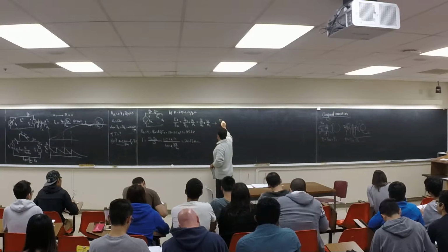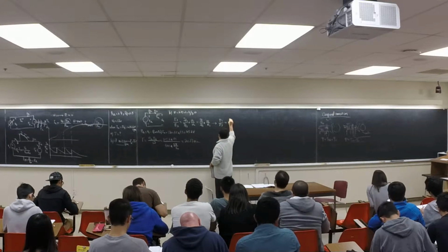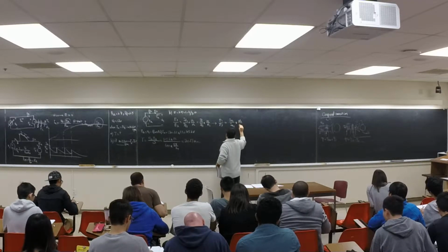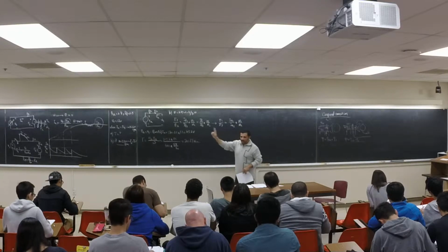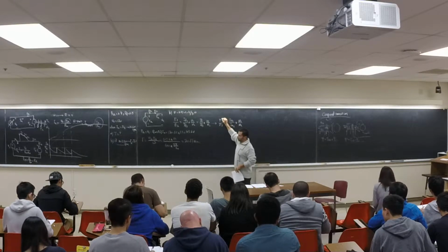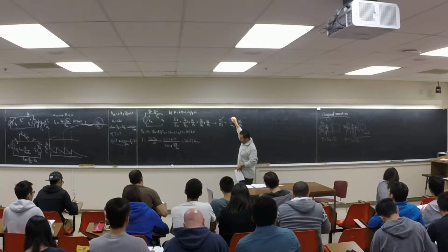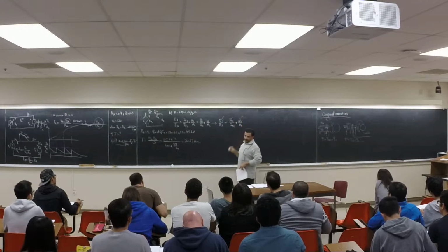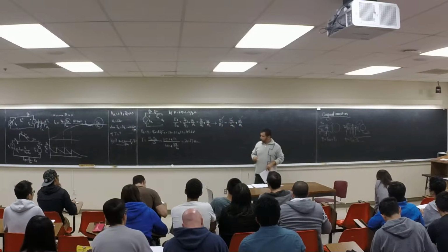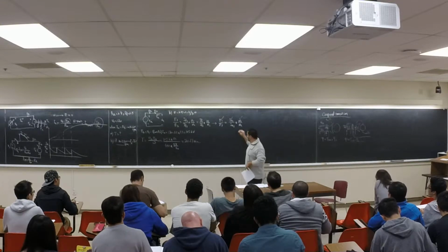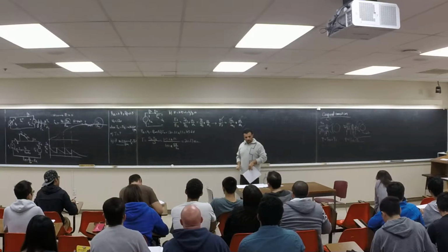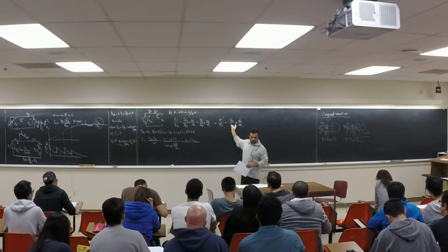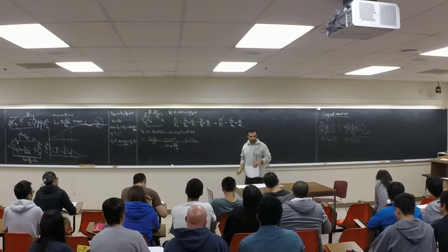So I can say E1 over E2 is IA1 over IA2 times N1 over N2, right? From part A, I know how much is E1? 105. How much is the IA1? I calculated it, yeah, 12 amps, right? How much is N1? 600 RPM, right? Now, part B said N2 is how much? 2400. Now I have two unknowns. If I can somehow find another equation, I'm done.